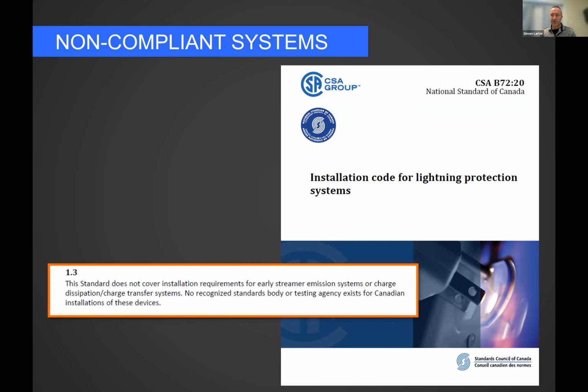Of course, we talked about why we use certain materials in a lightning protection system. The aluminum we'll use galvanized steel, painted steel, in contact with aluminum rooftop equipment, stuff like that, aluminum housings. And then the copper is the main conductor for down conductors. On a roof, we usually glue copper to a roof. We don't use aluminum, mainly glue to a roof, because it degrades faster in the presence of standing water. So if we have puddles on the roof, we're not going to be running aluminum through that, especially here in Canada. We get snow loads and moisture is in contact with that roof for a long time sometimes. So we'll use copper in those locations, and for the down conductor and for the grounding, because no aluminum below grade, that kind of thing, right?